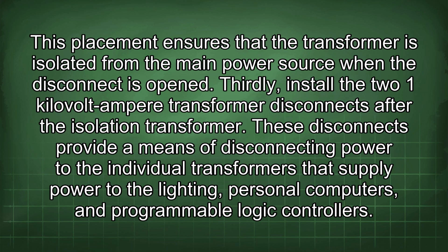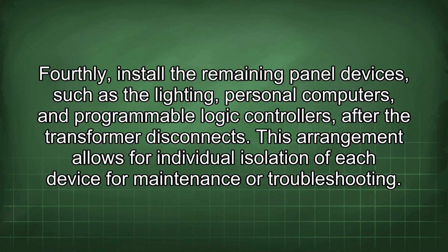Thirdly, install the two 1 kilovolt-ampere transformer disconnects after the isolation transformer. These disconnects provide a means of disconnecting power to the individual transformers that supply power to the lighting, personal computers, and programmable logic controllers. Fourthly, install the remaining panel devices such as the lighting, personal computers, and programmable logic controllers after the transformer disconnects. This arrangement allows for individual isolation of each device for maintenance or troubleshooting.